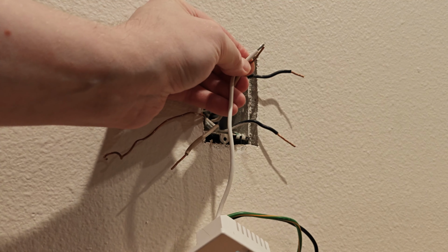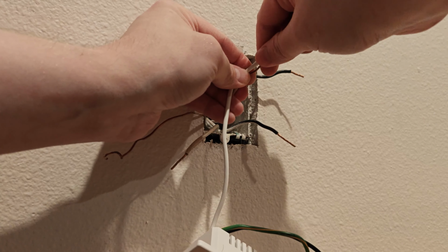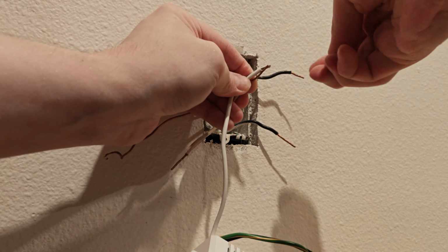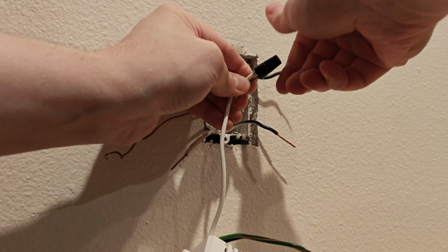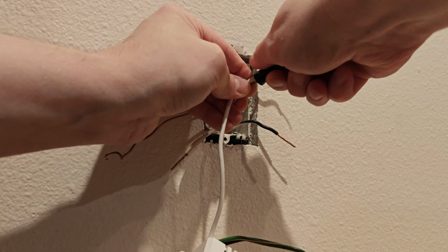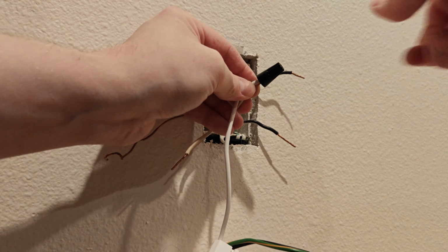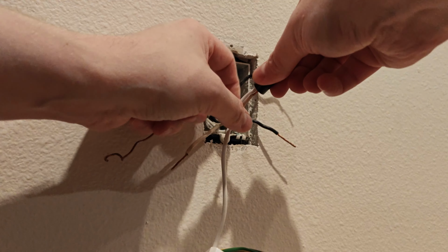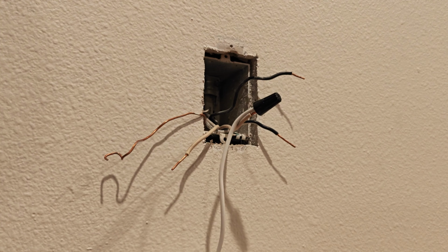Now, if you're using wire nuts, position the stranded wire a little higher so that it extends just a tiny bit past the solid wire and then twist them together clockwise. Place the wire nut on the end of the combined pair and twist clockwise until tight. You're going to want to give each of those individual wires a little bit of a tug to make sure that they're firmly seated and aren't going to pop out. Do this for all 3 of the wires.